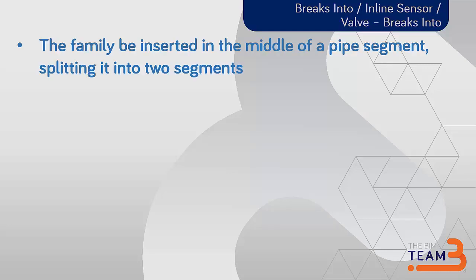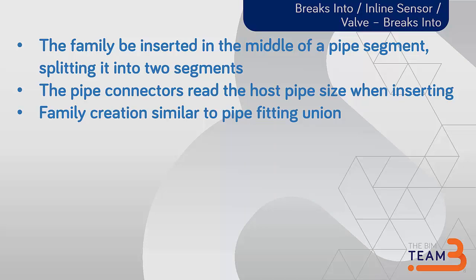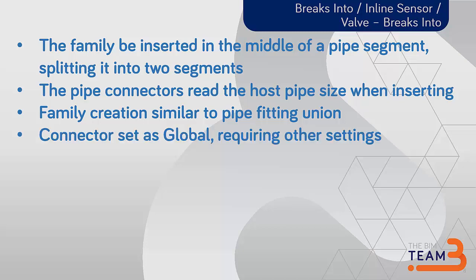The breaks-into and inline connector options: this family will be inserted into a pipe and will split it into segments, like a union for example. The pipe connectors can read the pipe size and adjust the size accordingly when inserting; after inserted they will not change. The family creation is similar to a pipe fitting union — you draw it horizontally with the axis on the reference plane, with a main connector on the left and a second connector on the right. The connectors can be set as global and require other settings, especially the K-coefficient factors for pressure loss or pressure drops.